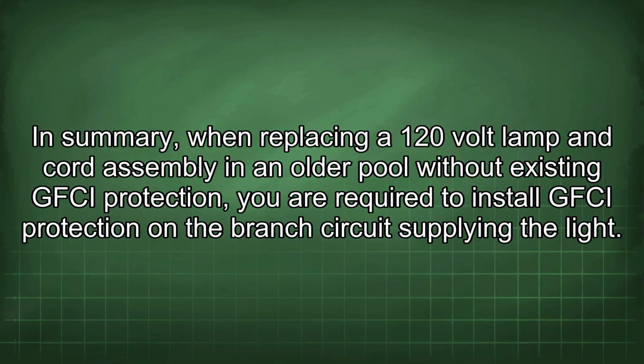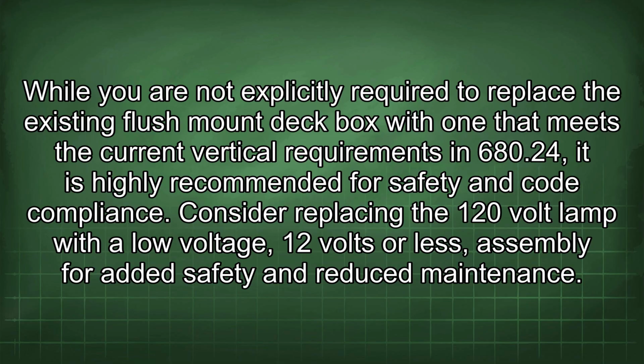In summary, when replacing a 120-volt lamp and cord assembly in an older pool without existing GFCI protection, you are required to install GFCI protection on the branch circuit supplying the light. While you are not explicitly required to replace the existing flush mount deck box with one that meets the current vertical requirements in 680.24, it is highly recommended for safety and code compliance. Consider replacing the 120-volt lamp with a low voltage assembly of 12 volts or less for added safety and reduced maintenance.